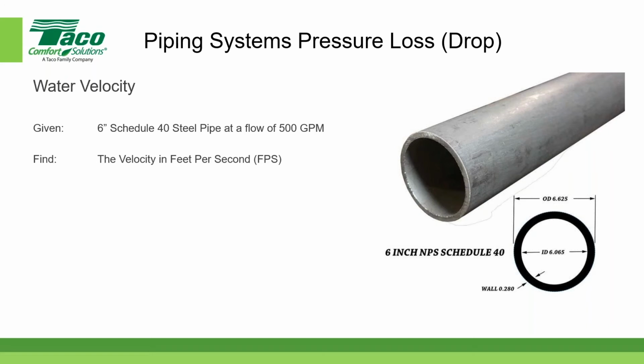But one of the very first pieces of information we need to find out is the velocity of the water that flows through whatever pipe you have in your system. So in this case, as I said, we're going to start off with a 6-inch Schedule 40 steel pipe at a flow of 500 gallons per minute, and we want to find the velocity in feet per second. So initially, we need to calculate the pipe internal area in square feet.